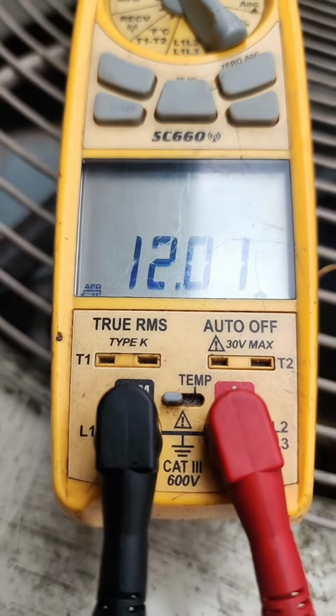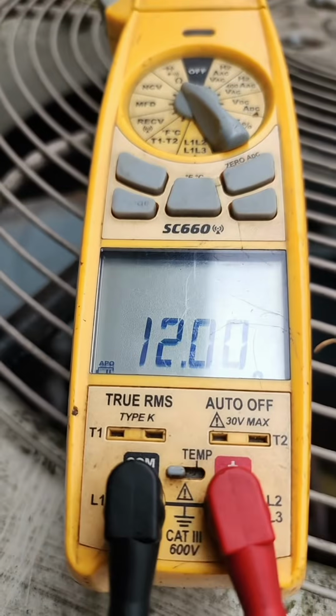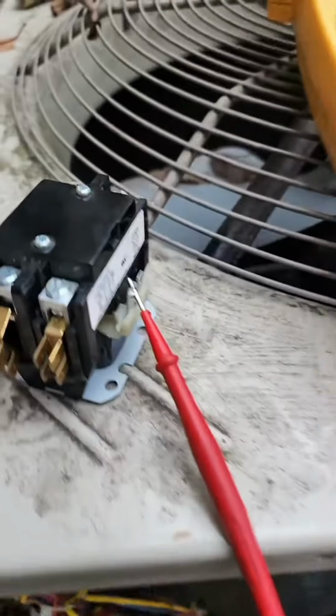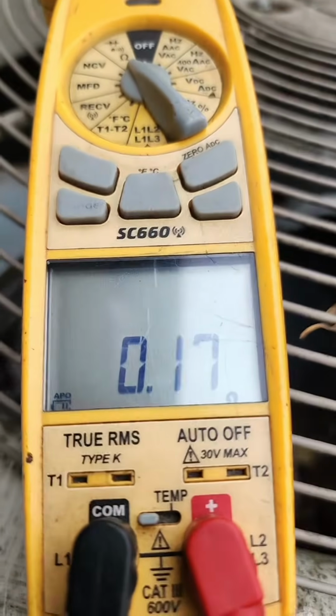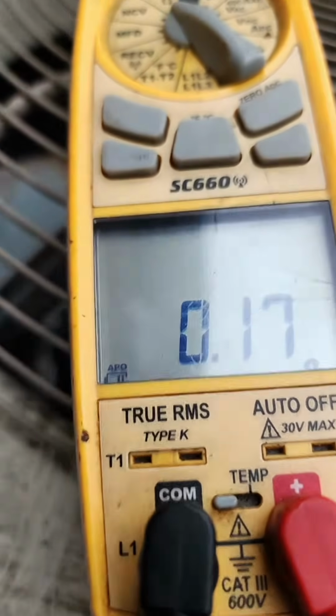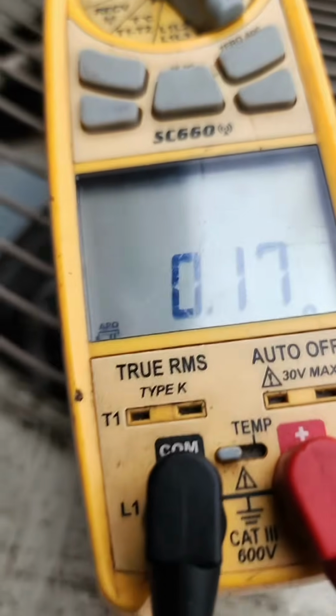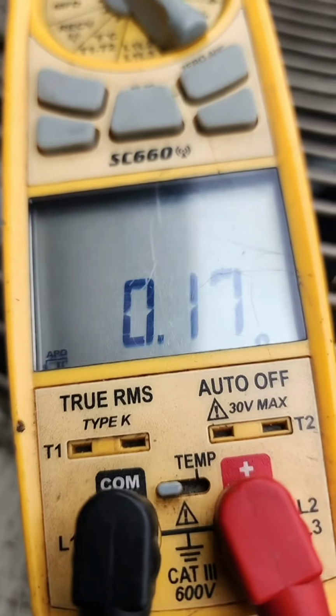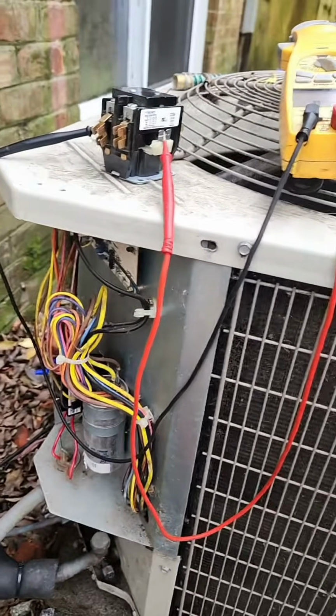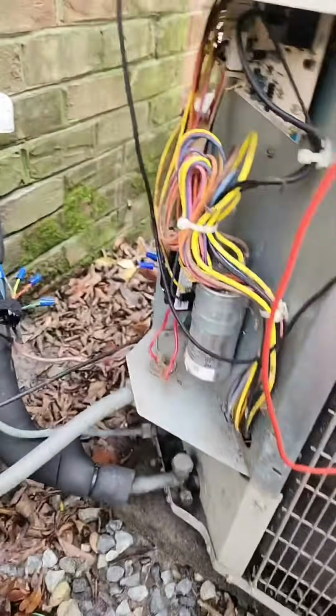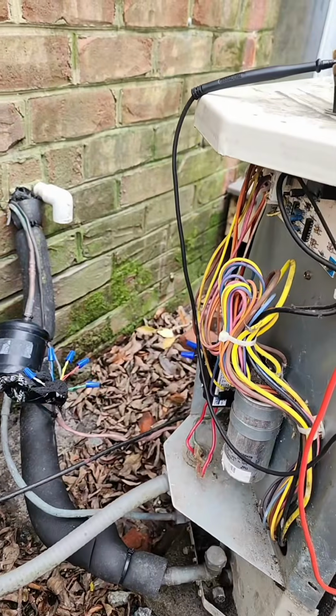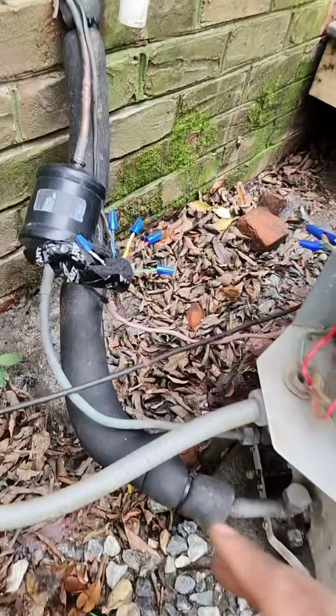So this is the new one. Let's get it in, and then we'll compare it to the old one. All right, this is the old one I just took out. Look at that, 0.17. So don't worry about anything on the right. It's the number on the left, so it should be between 10 and 20. But this one's shorted to ground, which is why I was blowing up the transformer. So this is the outdoor unit, transformer's in the indoor unit, but the thermostat, air handler, and the outdoor unit are all connected with the thermostat wires.